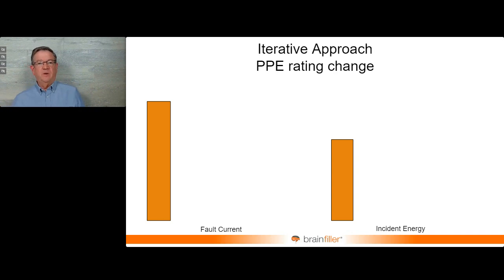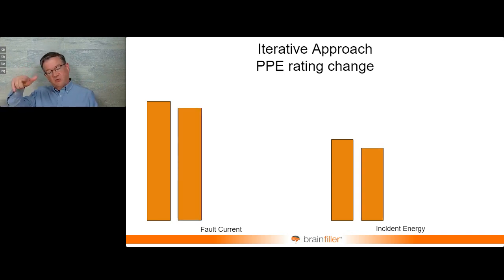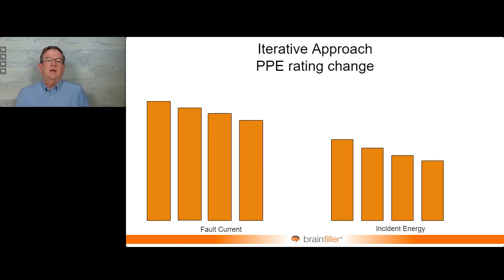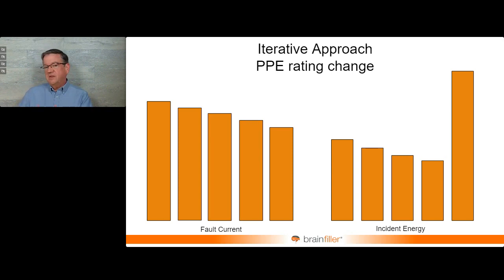So use what's called an infinite bus, figure out the short circuit current on the secondary side of a transformer, run the study, and see what the calculated incident energy values are. And note all the places where your PPE will be sufficient. And then decrease the short circuit current in incremental steps, 5%, 10%, something like that. And you'll see the incident energy come down, and do it again and again and again. And you'll decrease it one time too many, and you see the incident energy jump. What happened? The short circuit current went down low enough that one or more protective devices is now in the time delay region, and the incident energy went up.